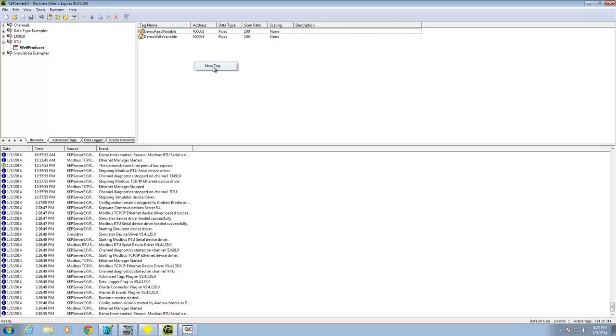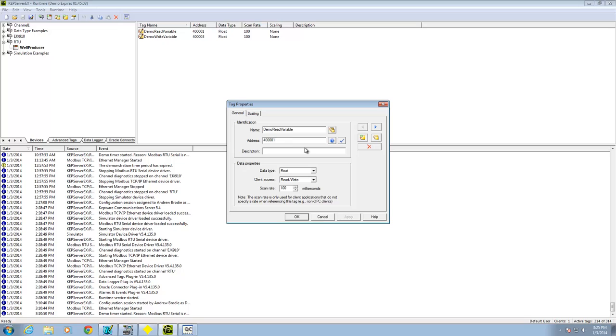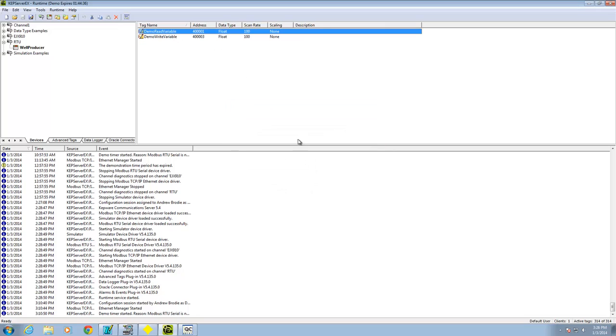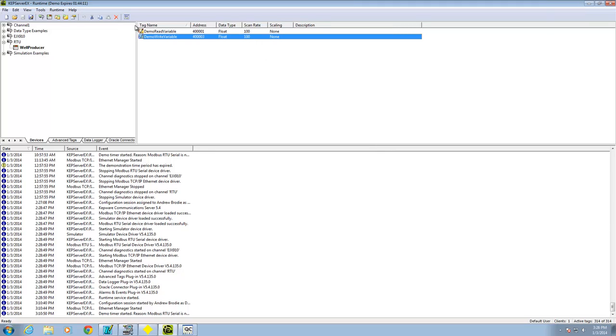Once the device is set up, right-click and go to New Tag. I've already created a couple. Give it any name you want. The address I'm using is 400001, and another at 400003. The first is the variable I'm reading, and the second is the one I want to write to. The data type is float. You can leave it as read-write. Then for the second tag, the address is 400003. This is necessary because it takes two words to represent a floating point variable — so 400001 and 400002 are used for the read variable.